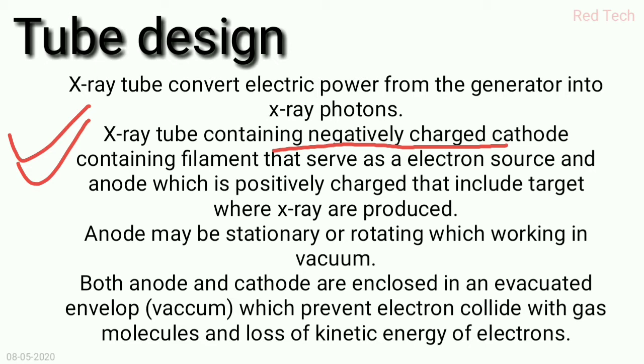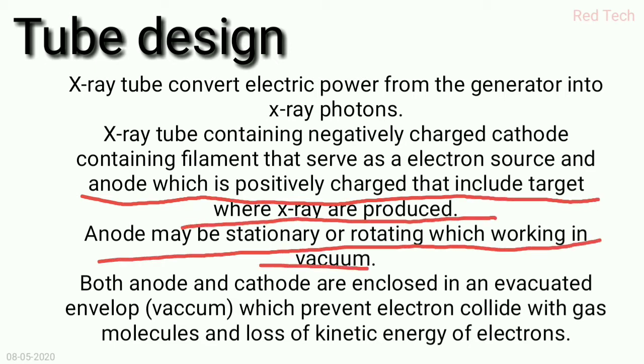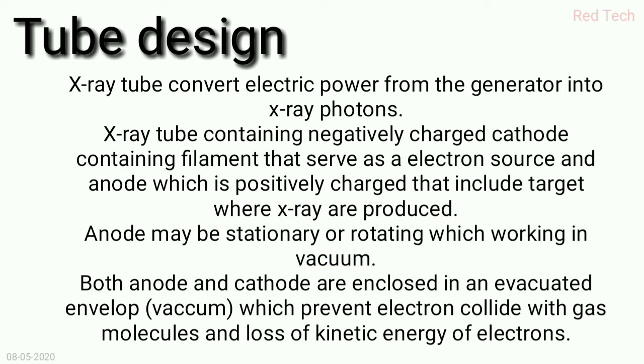The x-ray tube contains a negatively charged cathode, which contains the filament and serves as the electron cloud source, and an anode. The cathode is negatively charged and the anode is positively charged. The anode is basically the target where x-rays are produced. The anode may be stationary or rotating, and both operate in vacuum.